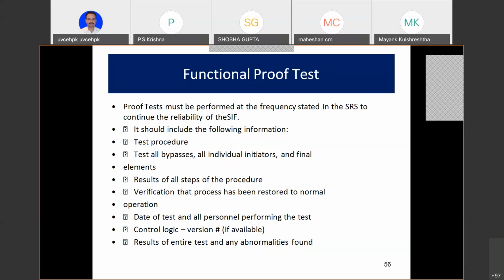So the proof test is done as prescribed, and that number is arrived at by calculation. The proof test period is built in, like I told you, the university people get credit: you do this course and you do an extra course on artificial intelligence, you get credit so that your value starts going up. In the same way, you can improve the quality of safety action by doing proof testing. Very good question. I'll tell you why. I just explained the pressure switch which failed because the welding of the micro switch had taken place. That you will never find unless you do proof testing. Proof testing is the savior, actually.